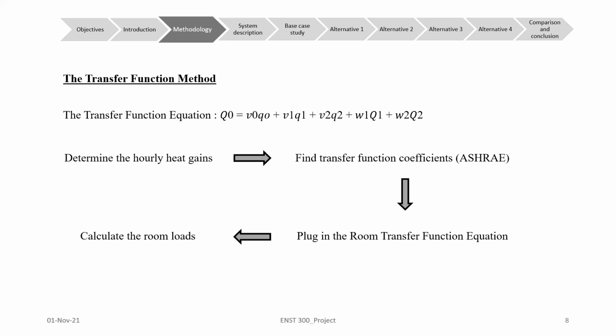Values of these coefficients, small omega and small v, vary for each type of heat gain and each type of room due to different heat transfer processes. We get them from tables published in ASHRAE for different heat gain components, room types, and building weights. So this method allows for easier calculation of the room load since it consists of four easy steps. First, the user has to determine the hourly heat gain. Then find the transfer coefficients from ASHRAE, as I said, small v and small omega, plug them into the room transfer function equation, and finally get the room load.